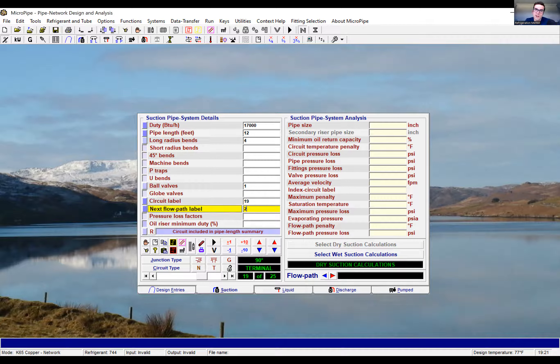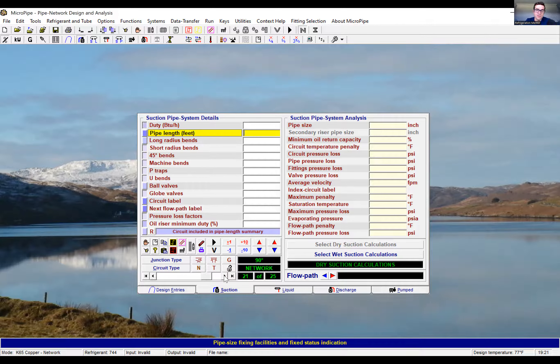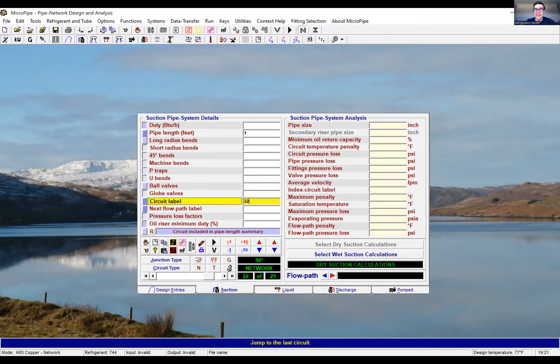You look at compression ratio and it depends where you're at. Here in Canada you can be in subcritical all the time. When you add heat reclaim and hot gas — when you put it all together — your CO2 is more efficient. So it all depends on the application. From what I've seen and all the studies I've read, it all depends on the application. It's great to share these studies — comparisons aren't always what they seem, because we might be measuring a brand new system against a 10–15 year old system that hasn't been maintained particularly well.